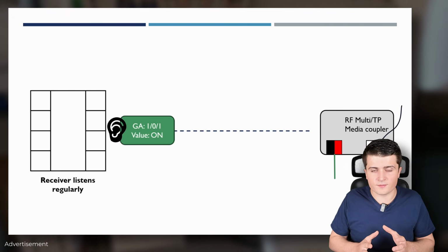So what this means is that if you have a battery-powered device, this battery-powered device typically sends fast communication because it wants to send its information fast so that it can sleep as soon as possible. But it receives slow communication so that it can sleep as long as possible for the receiving communication. So now you saw the innovations that come with KNX RF Multi.